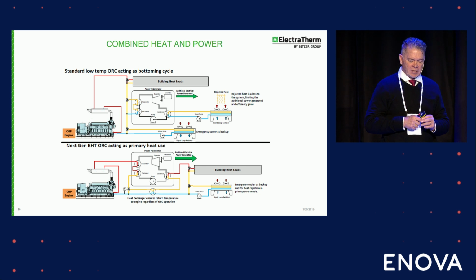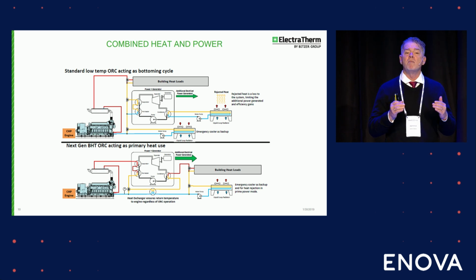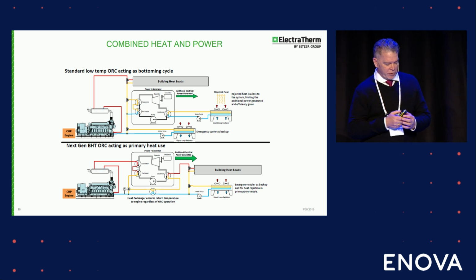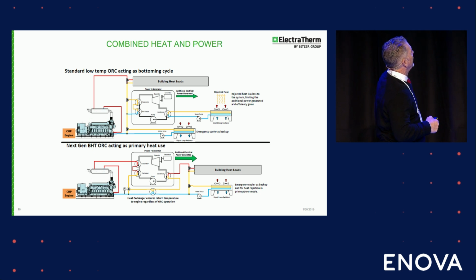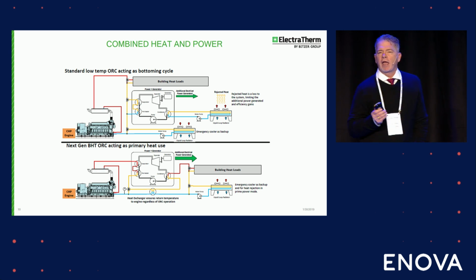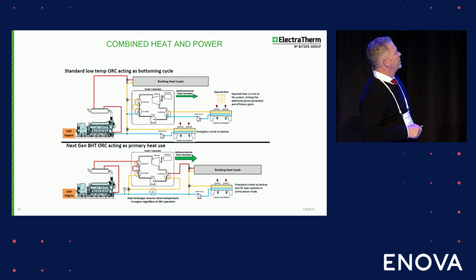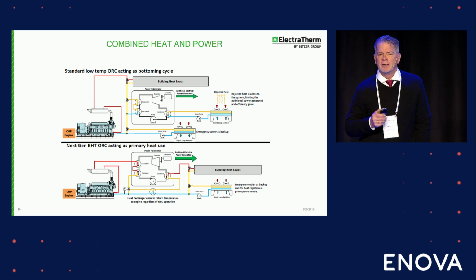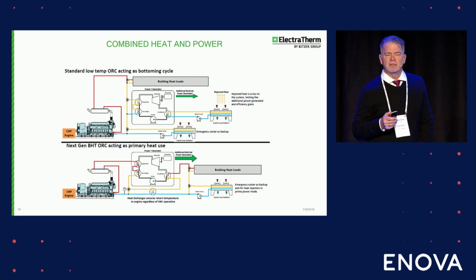We've got a next generation coming up, called the BHT. It shows the organic Rankine cycle working as a primary heat use. We're taking the heat in, and because we can now run at elevated temperatures, we can give the desired building heat load what they want—maybe 80 or 85 C. In the past, we couldn't bring this higher temperature to the building loads because we were limited by the pressures inside the system with our old expander. But with the Bitzer expander, we can go to higher temperatures, allowing us to move to higher power generation and also offer higher condensing temperatures for building use.